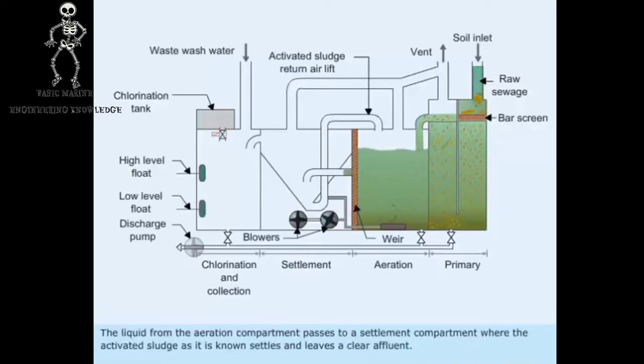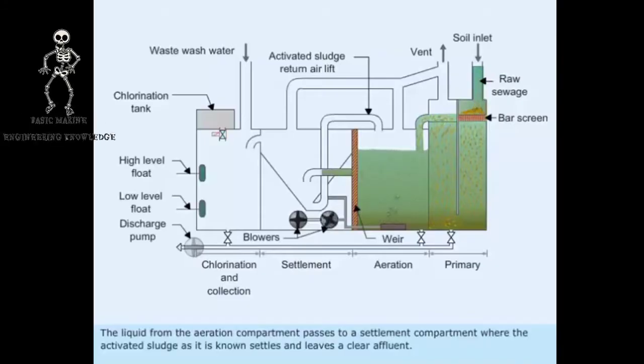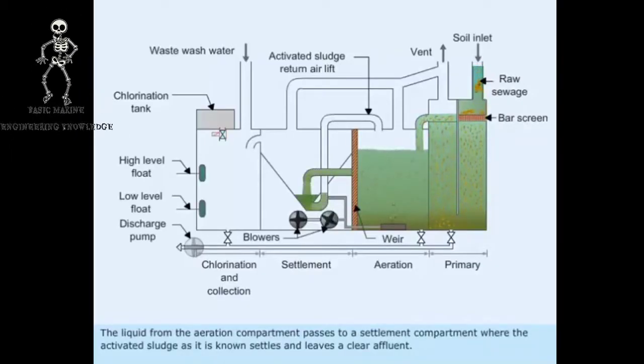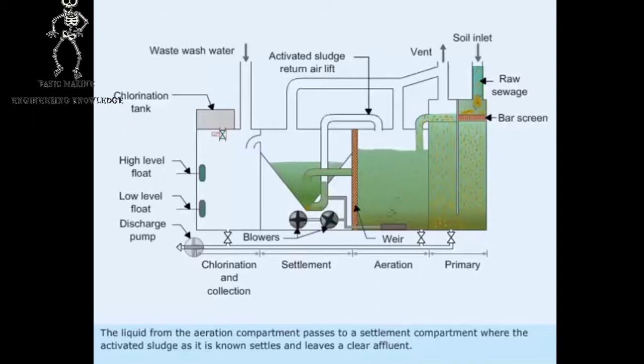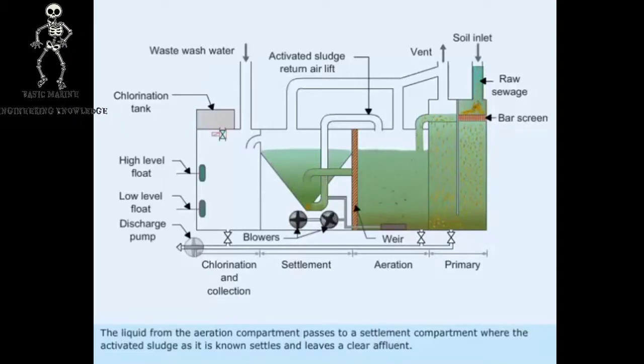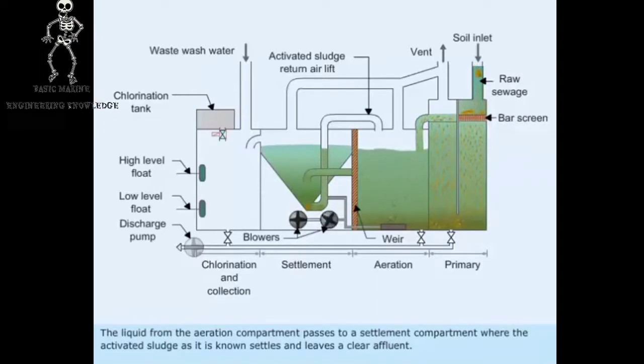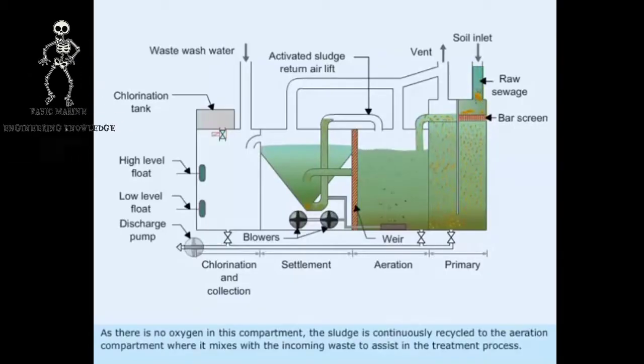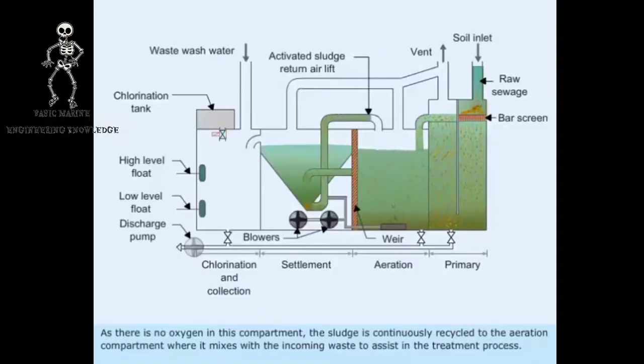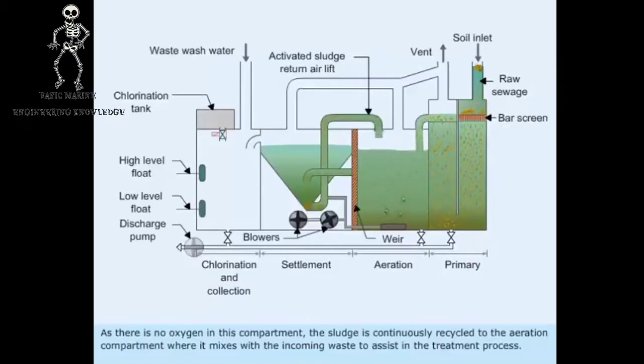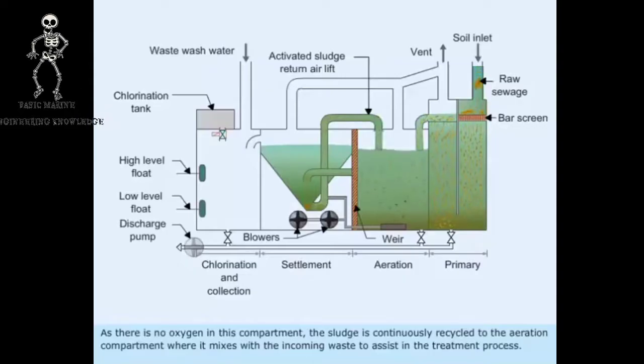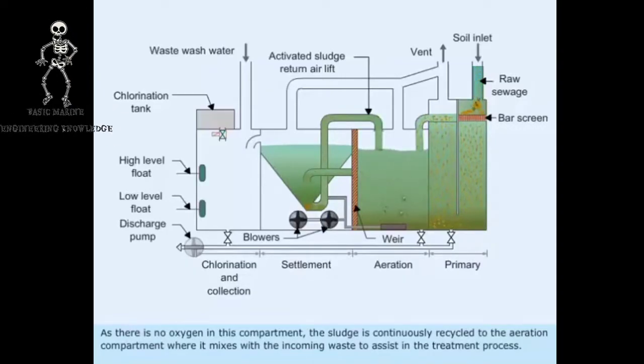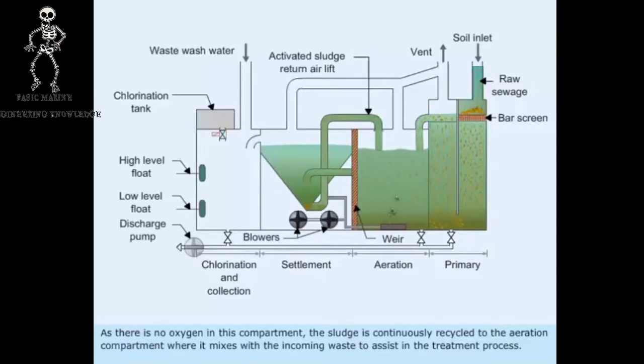The liquid from the aeration compartment passes to a settlement compartment where the activated sludge, as it is known, settles and leaves a clear effluent. As there is no oxygen in this compartment, the sludge is continuously recycled to the aeration compartment, where it mixes with the incoming waste to assist in the treatment process.